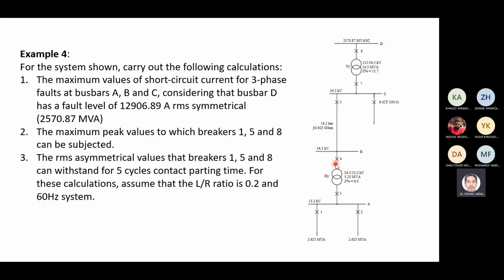At each bus. بالتالي هذا نسميه إحنا symmetrical steady state current. ولما نطلع هاي عادة في الكالكوليشن أنا بحسب بس الورست كيس سيناريو لما أمثل كل الاليمنتس باي ذير اندكتنس، يعني أهمل الريزيستنس عشان يكون عندي even higher short circuit current.